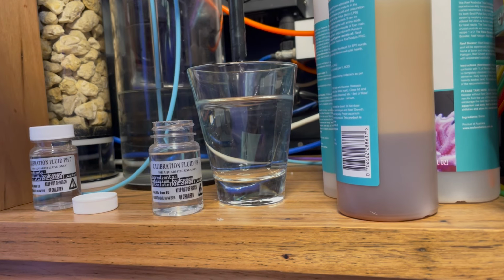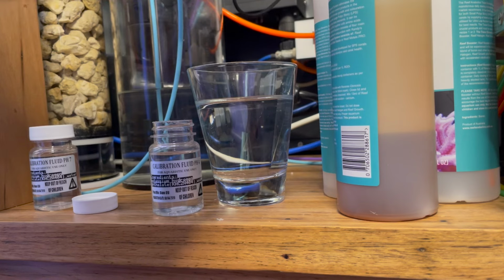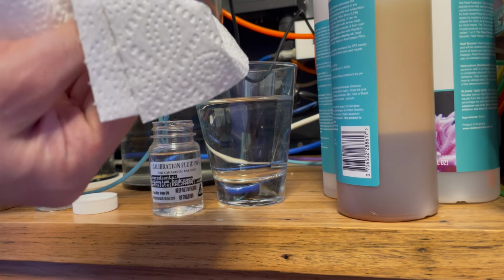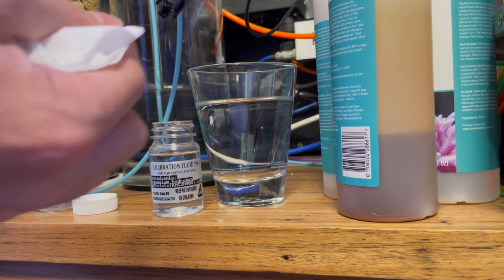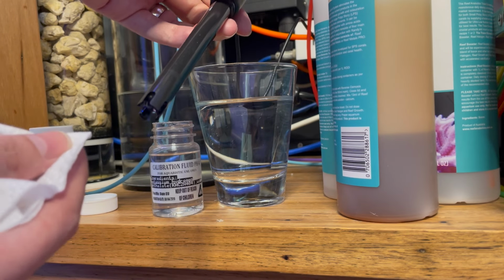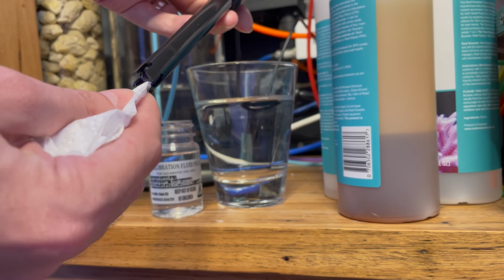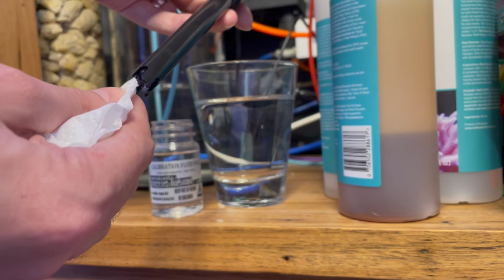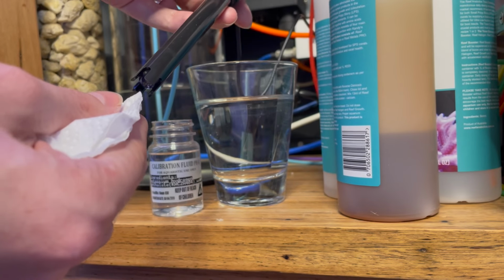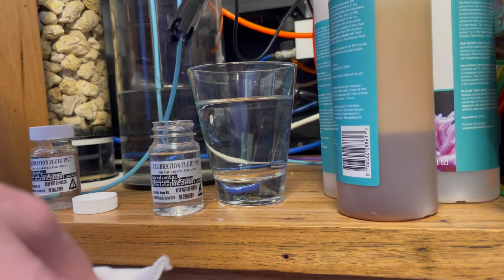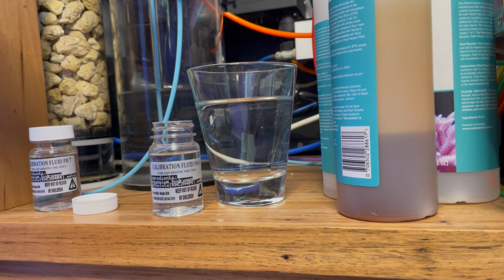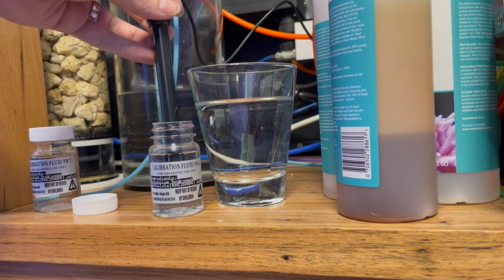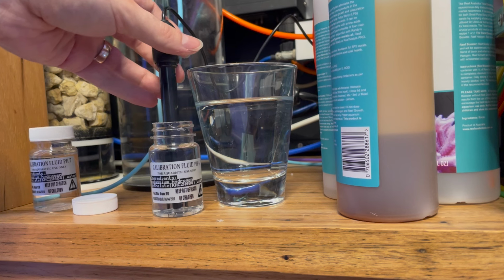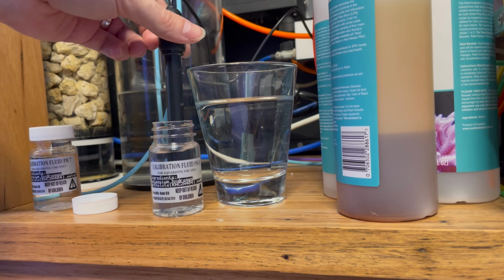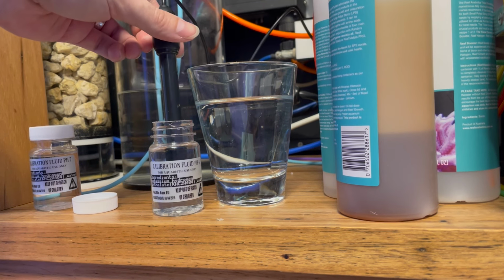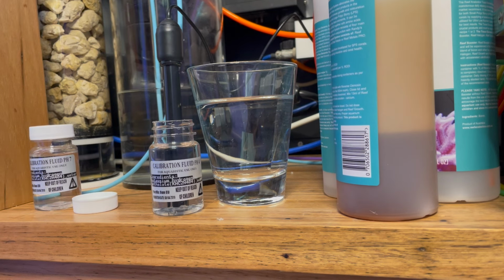Now we'll take our pH probe. I'm just going to gently dry off the RO water using the paper towel. And you just want to dab the glass bead very gently with the corner of paper towel just to soak up any excess liquid. You don't want to rub the glass bead. And then you simply put it in the bottle of pH 4 liquid, give it a little shake to make sure there's no air bubbles trapped on it. Simple as that.